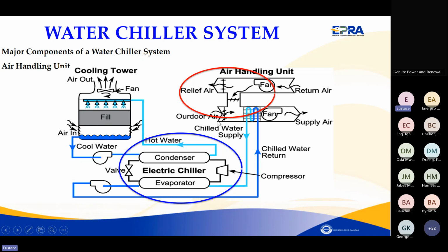And especially since a cooling system and air conditioning system is designed to work at the optimum point, at the extreme point. But sometimes you have temperatures from outside going low. And you find in some cases, the chiller is running even when the conditions outside are favorable to use the outdoor air. So you need to establish that exactly from here so that you can know how to control your chiller to reduce the amount of energy it is consuming at any particular time. The same case, or you can decide to use the cooling tower directly without running the chiller to save energy. We are going to see that one through an example.